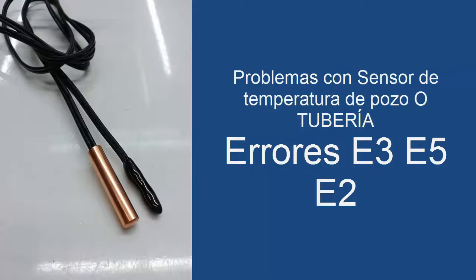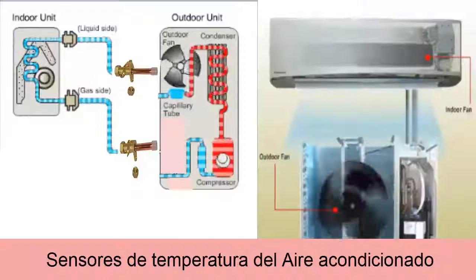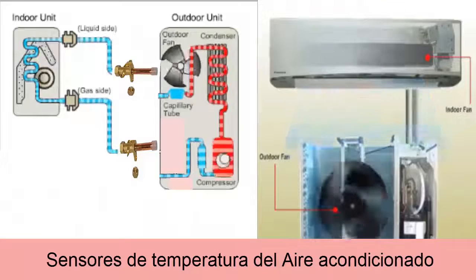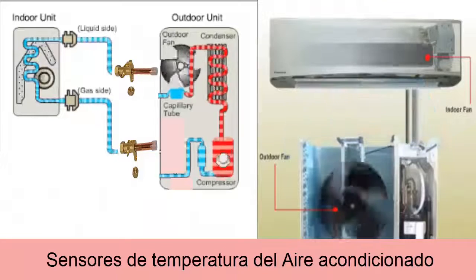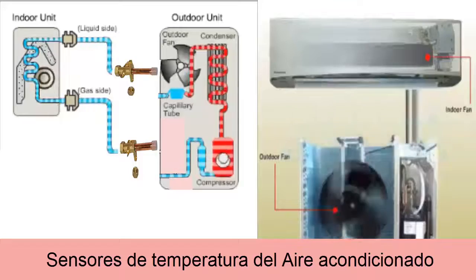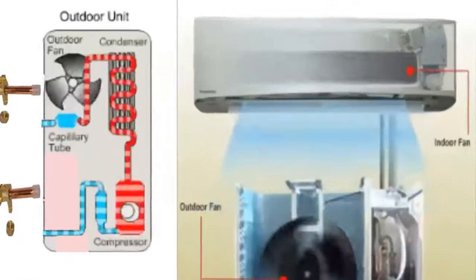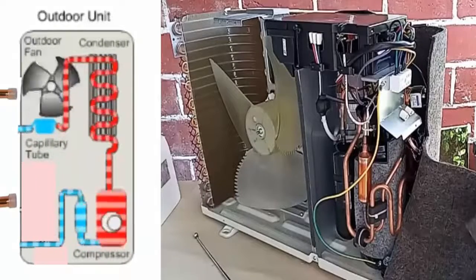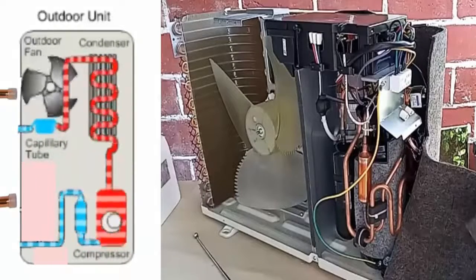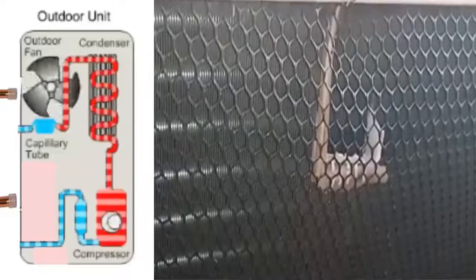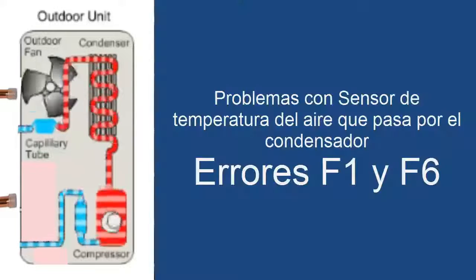In addition to these two sensors, which are the ones we will find more often, we can find other types of temperature sensors. At the condenser, we can find a sensor that measures the temperature of the air that passes through it. When this sensor has problems, we will find error codes F1 and F6.